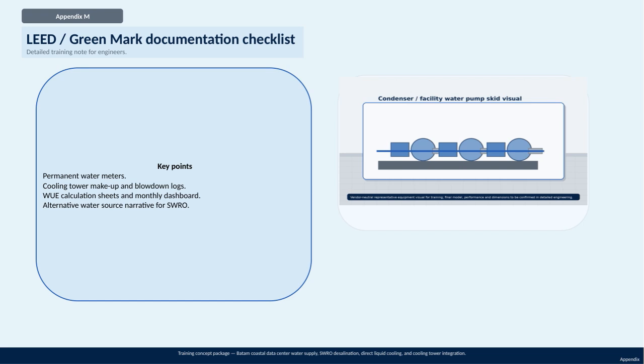Some of the key points to keep in mind are the installation and monitoring of permanent water meters, maintaining accurate logs for cooling tower makeup water and blowdown, and using water use efficiency calculation sheets alongside a monthly dashboard for ongoing performance tracking. Additionally, it's important to have a clear alternative water source narrative specifically addressing the SWRO system to support our sustainability goals. This appendix is designed to help engineers understand and document these aspects thoroughly and consistently.